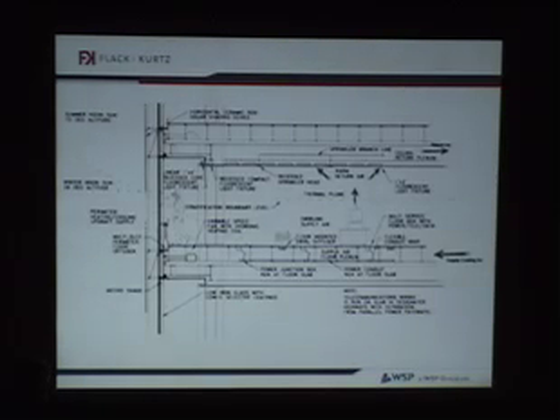Where the cruciform extends out from the core, we initially thought we needed to extend fingers out to make sure air got out to pressurize all aspects of the floor. With an underfloor air system, unlike an overhead system, we have to look at the ductwork layout and its efficiency. The key is really how you get air into the floor and how it fills up the floor so it comes out uniformly across the entire space. Here's a quick cross section.